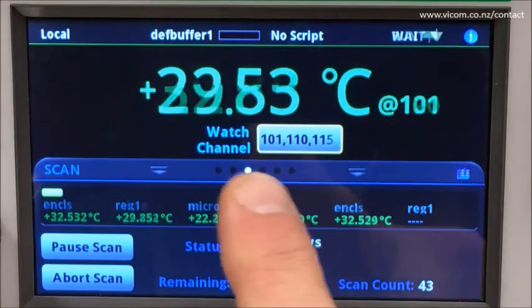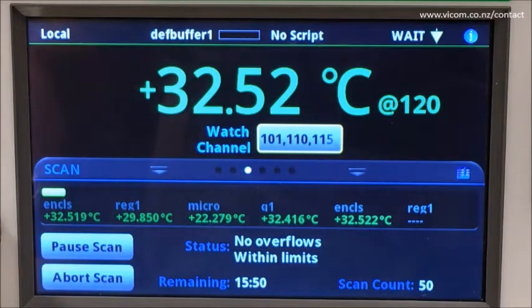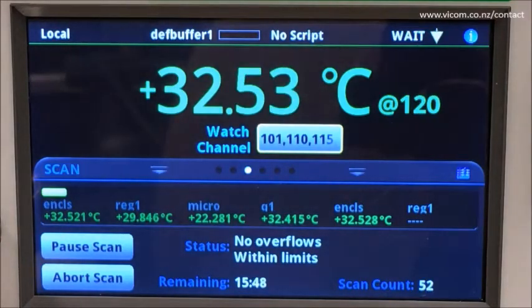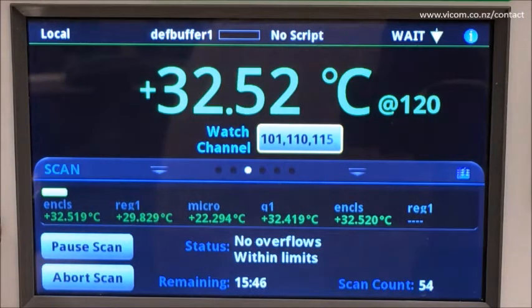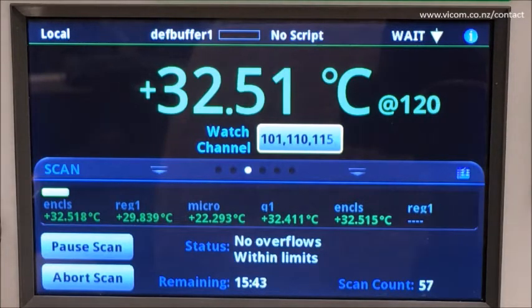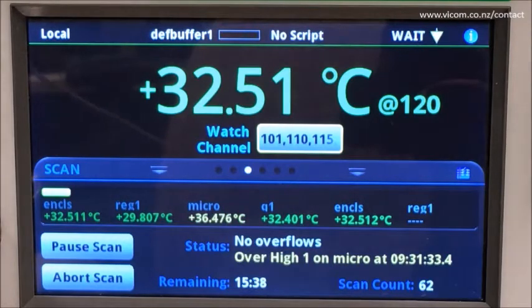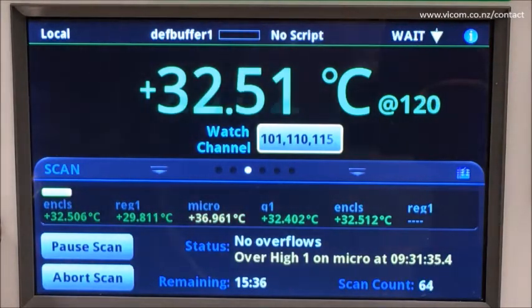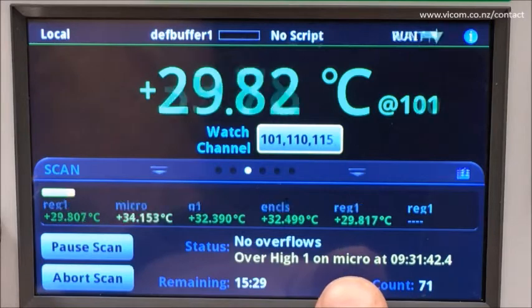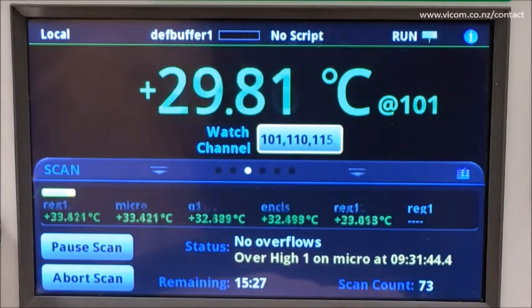You can also see in the measurement window that as the instrument is taking measurements for each individual channel, those are displayed in the main area. Let's observe what happens when we hit a limit condition. Here you notice that we're told on the front panel what the condition is — the microprocessor is getting hot — and we hear the audible alarm.